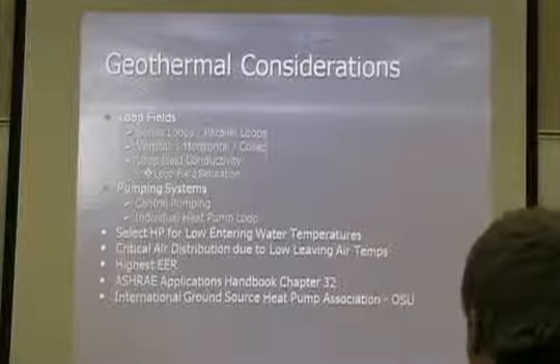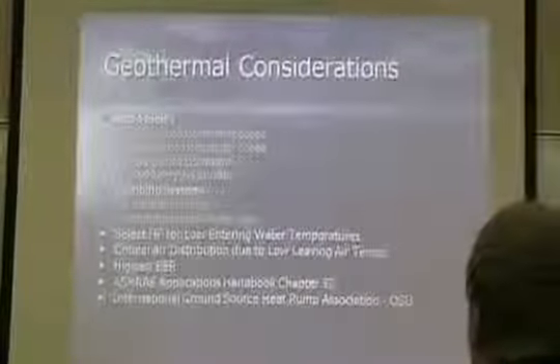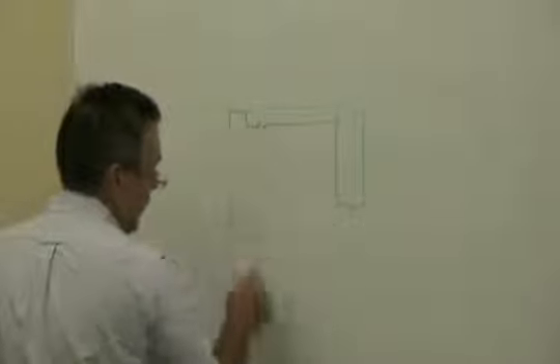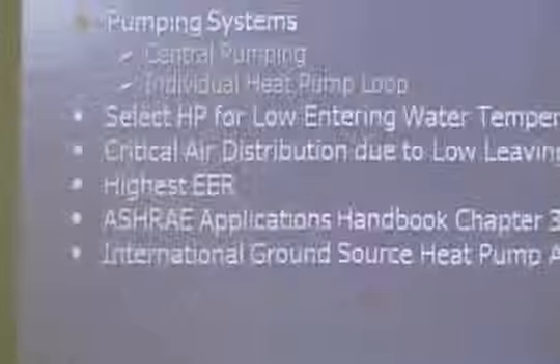You can also have that loop. A lot of people, especially in geothermal loops, have a series of heat pumps. They'll put the little individual pumps on each heat pump. They might actually go to a well and right back into the building. Generally, that's about the only time you put the individual pumps on the units, when you've got an individual little drop in a geothermal application. Most water source heat pumps, you're going to use a central pump, again because these little bitty 2, 3, 4 gallon a minute pumps are 60% efficient. Bigger pumps get up to 80% efficient. Select heat pumps for low entering water temperatures.